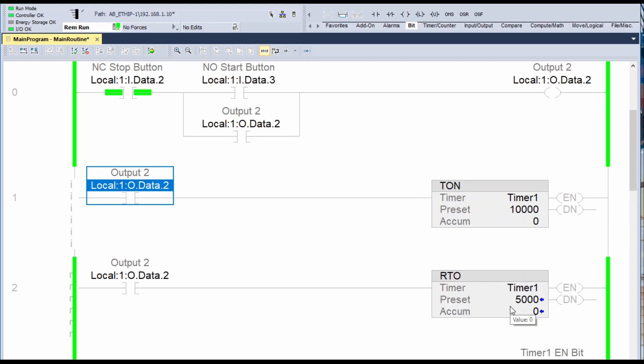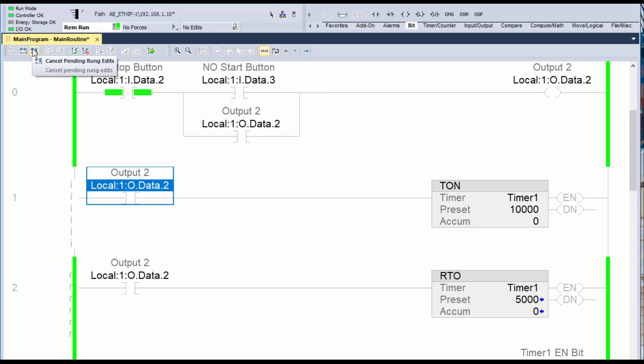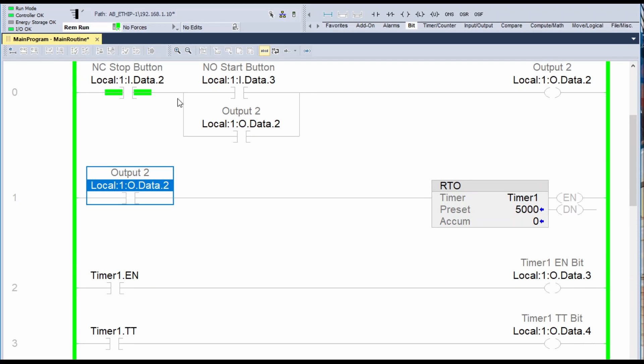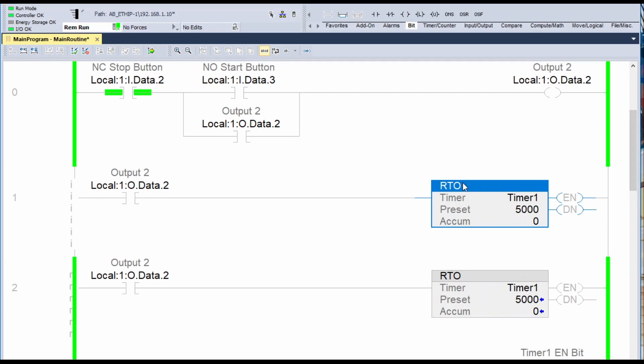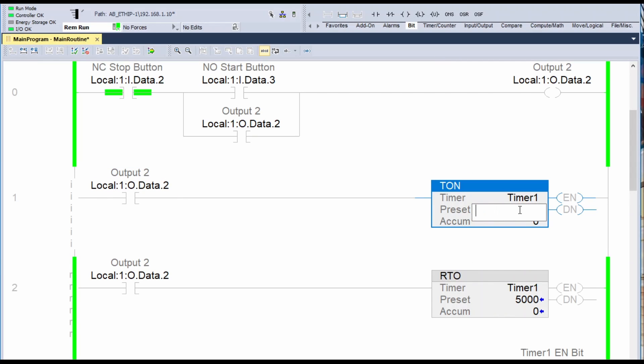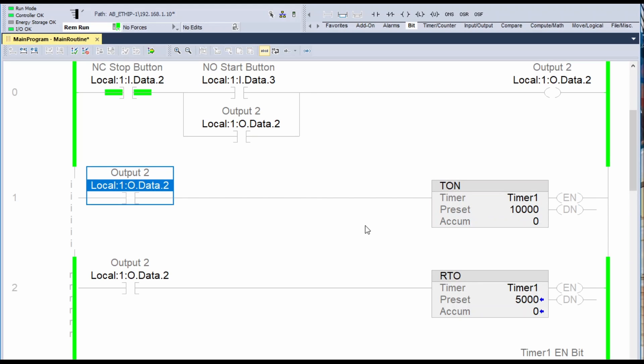You can see that my previous rung is here and my new rung is here. The next thing I'm going to do is accept the pending rung edits. But if I screwed up and hit Enter by mistake, I could hit Cancel Pending Rung Edits — let's do that just to show you. So if I do Cancel Pending Rung Edits, it just goes back to normal. So I would go back here, change this to a TON timer, and change this to 10,000. Keep in mind that these values are in milliseconds, so now I'm going to have a 10-second on delay timer rather than an RTO.